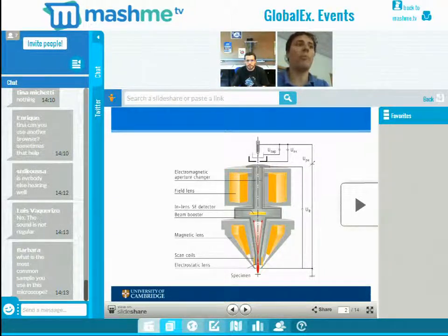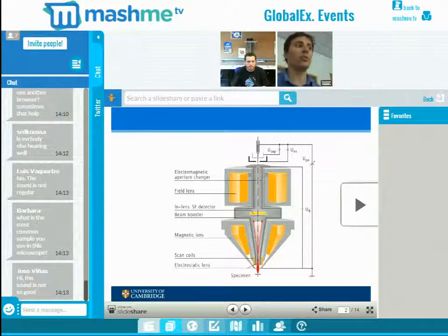And depending on how many electrons the detector detects, the pixel you see on the computer gets brighter. So the number of electrons detected per spot gives feedback on the monitor. If a lot of electrons are scattered, the pixels on the monitor will appear brighter. So that's how you actually get the image in your scanning electron microscope. While scanning, you look at all the different spots, and then you calculate the whole image.